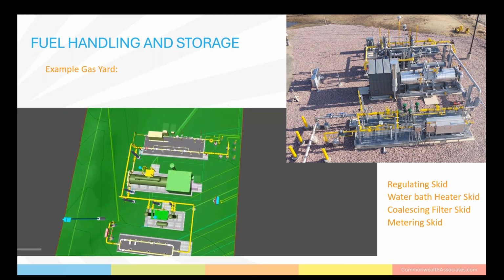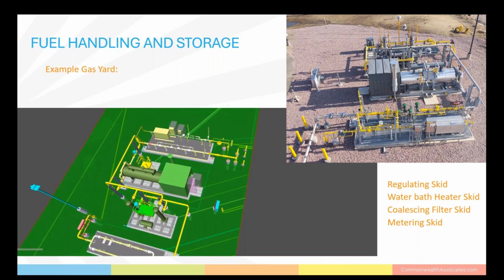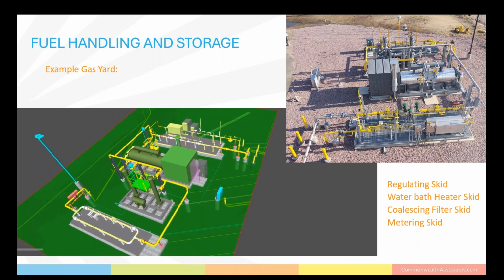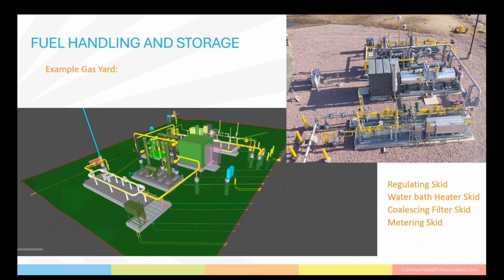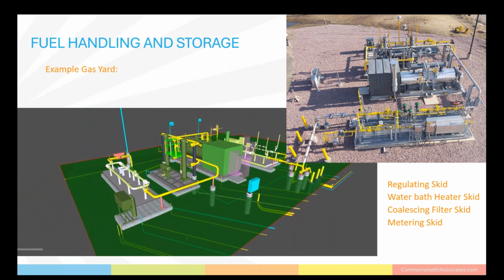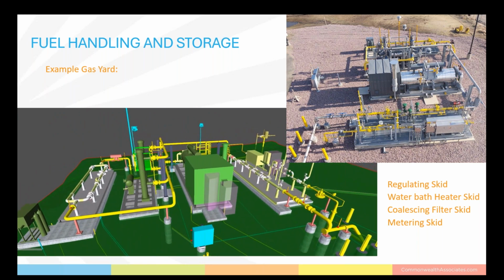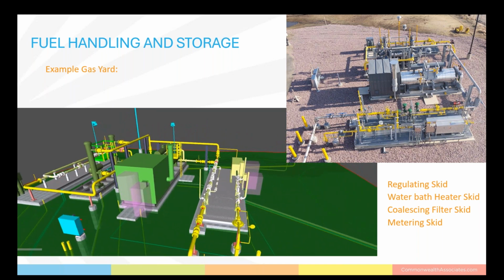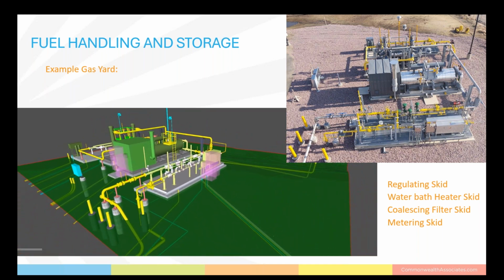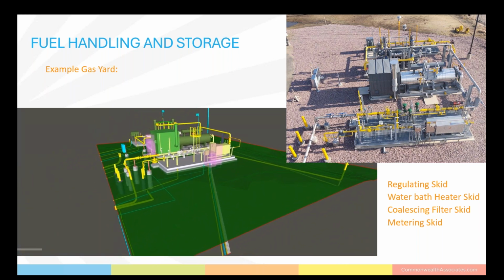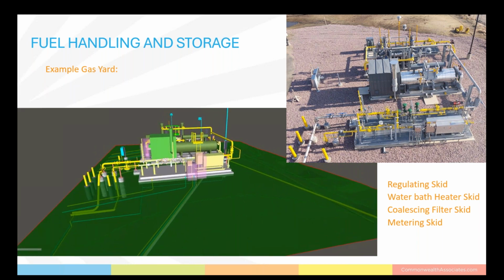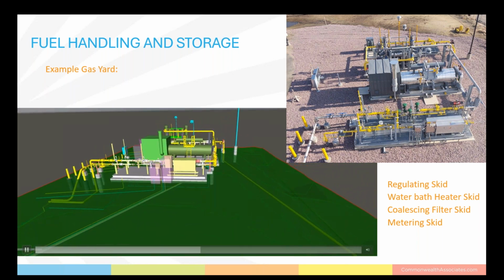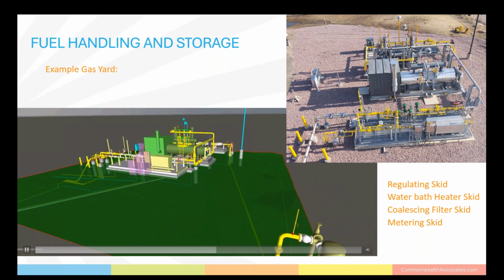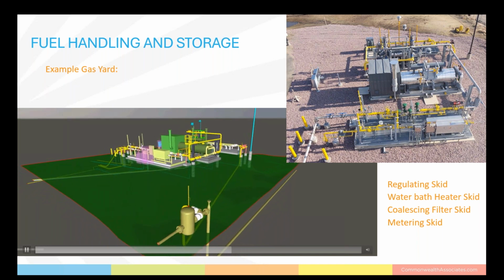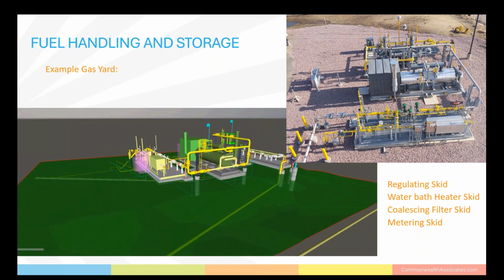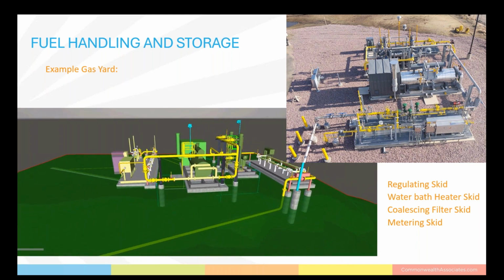What you see moving on the left is a 3D model of the layout that was used to create the previous slide. This design takes care of those fuel quality considerations. What we see here is a regulating skid, a water bath heater skid, coalescing filter skid, and a metering skid. In the upper right, we have the real world picture of the finished design in place and operating. And while this runs, I want to mention that you can see underground, we've routed all the underground piping and conduit. This is one of our methods to make sure that we have 0 interferences while we're designing these plants. I like to let it run because it's fun.